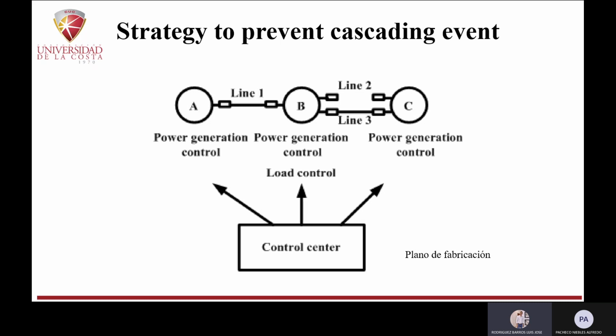Current stability control devices cannot solve the problem of the cascading event as shown, but the global stability control system can obtain the whole information of the system, protection and stability control devices, so it is possible to solve the problem, as reflected below. If the case is a fault occurring in line 1 or line 3, the corresponding main protection will act and trip its breakers. The action time of main protection is about a few tens of milliseconds. The control center receives the protection action signal from line 1 and line 3. It then analyzes that the power flow increases on line 1 and line 3 during this time. So the analysis is performed with the added new information in the control center.